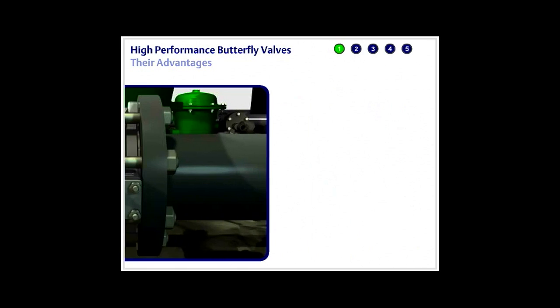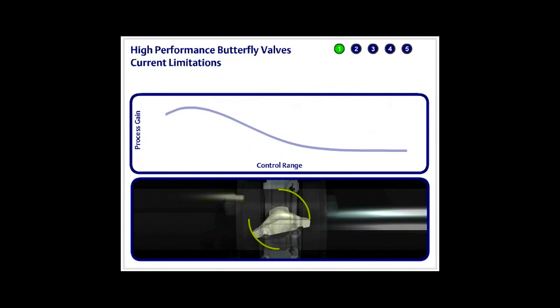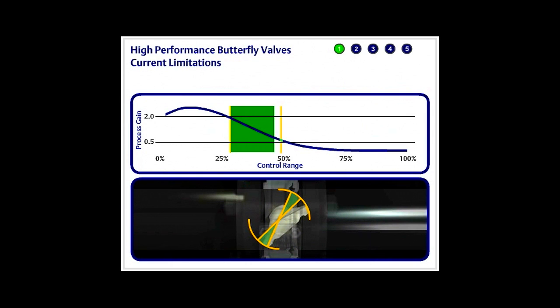However, the majority of industrial applications involve fast processes and varying pressure drops, situations in which the butterfly valve performs poorly. This lack of control can also be seen at both low and high flow rates, which means the butterfly valve's effective control range realistically occurs between 30% and 50% open.